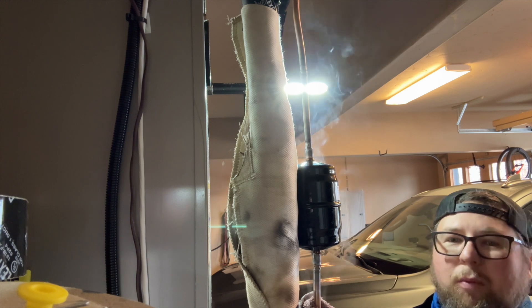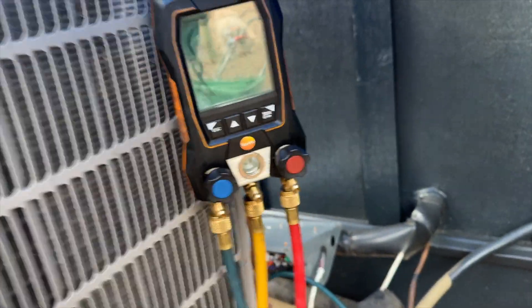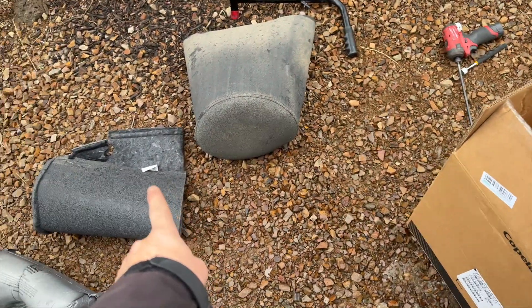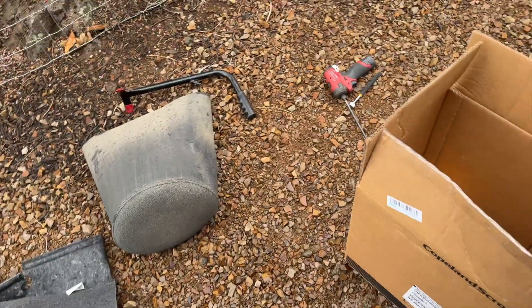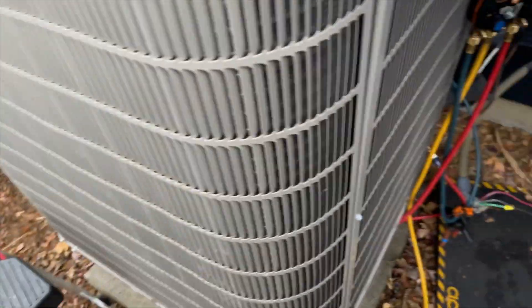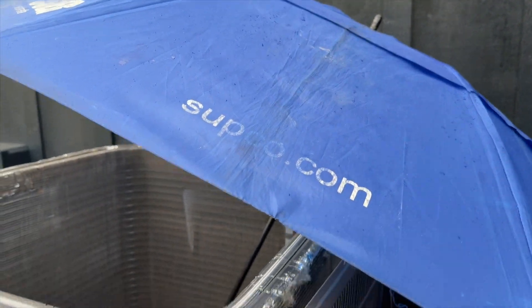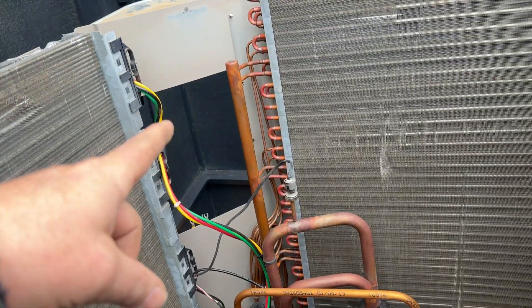We're doing our final pressurization. We need to put everything back together and then install that inverter. This one actually has two blankets - one goes over the compressor and then the other goes over that and the compressor. They want to make sure it's super quiet. While I'm waiting for this to pressurize I'm going to put the bolts in and plug everything in. Started to rain a little bit, so I set this up to keep it off the control board.